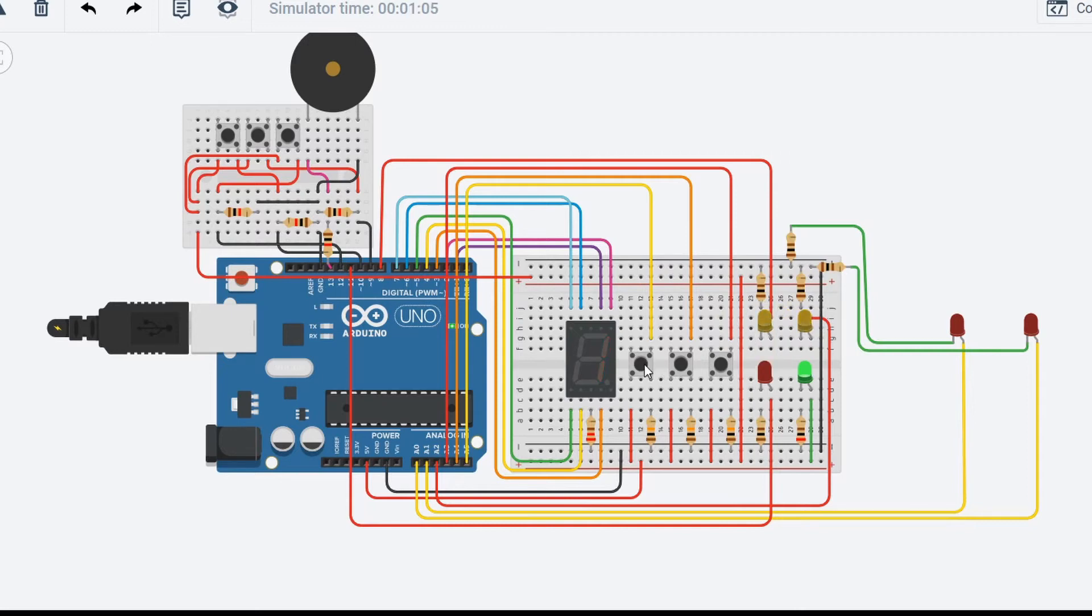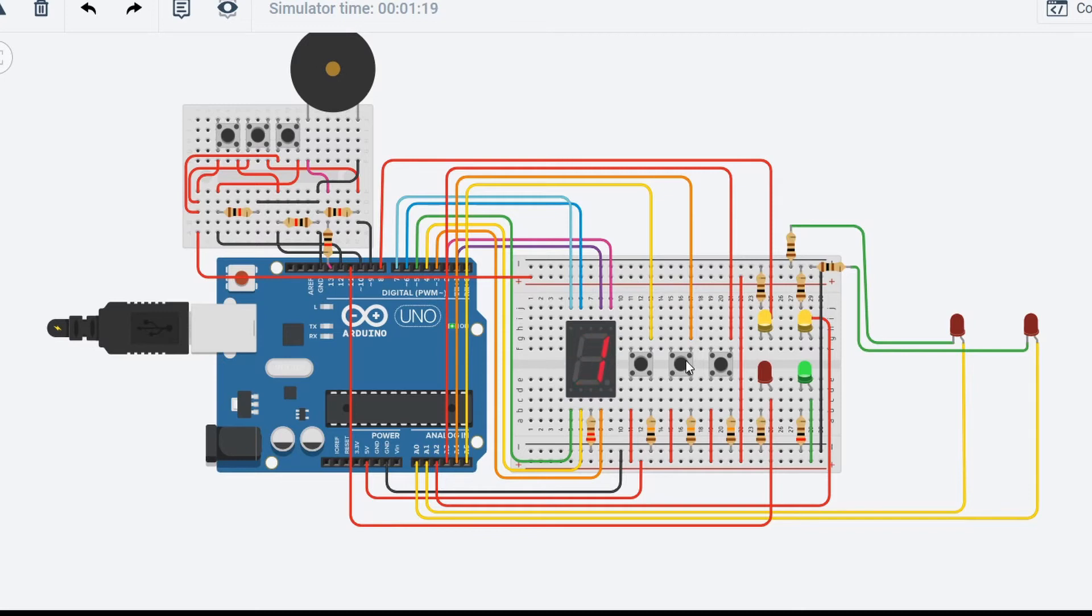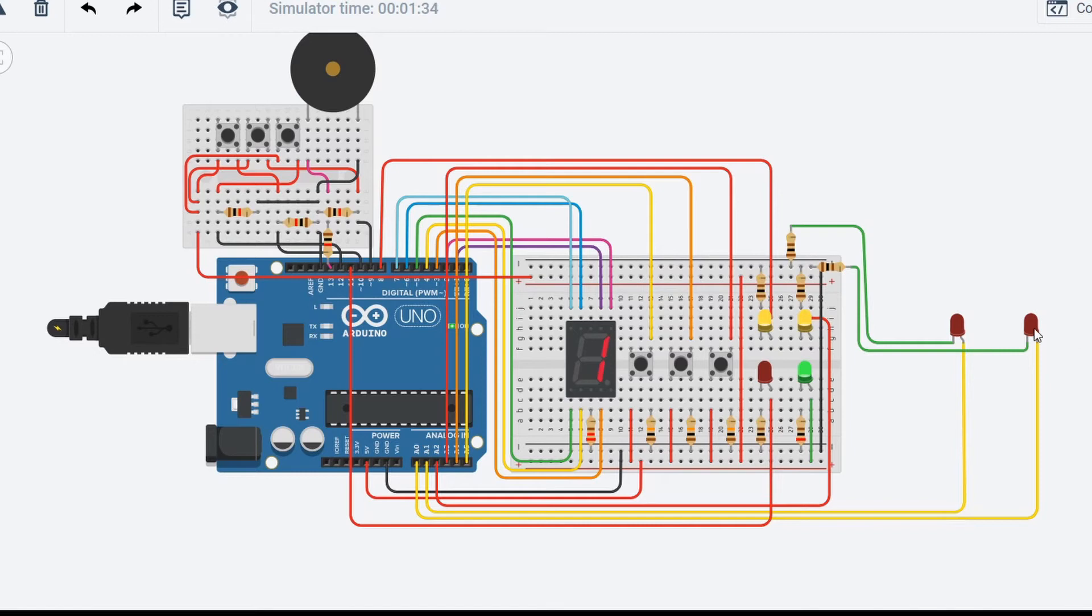And then option menu two is two LEDs. So as you can see, when I go into the menus, the seven-segment display displays a one right now, and that's because the default selections are one. So if I up this, this is coding. Three is set to march time. And then this is whether you want the NAC or the strobe to put out a sync protocol. It's just a basic one. It'll just flick off for a split second. So this is the strobe LED, and this is the horn LED.